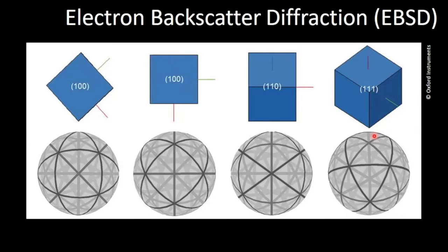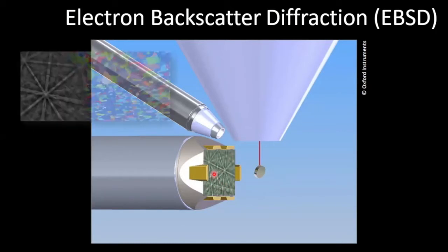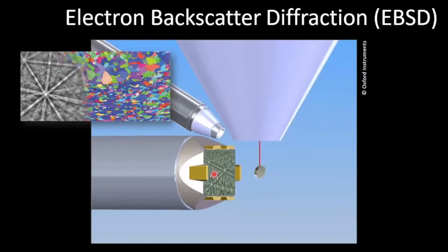If we wanted to simplify that, we talk about the different indices in a crystalline structure — for geologists we call these Miller indices — the different axes within a solid material that all intersect with each other. Here are some examples of common patterns: the electron backscatter pattern and the crystalline axis it represents. If you look at a cube and rotate it, depending on which face you're looking at you see a different pattern. The EBSD detector is looking for those different Kikuchi bands on the phosphor screen. Thankfully we have clever software that can translate those patterns into maps of your specimen.